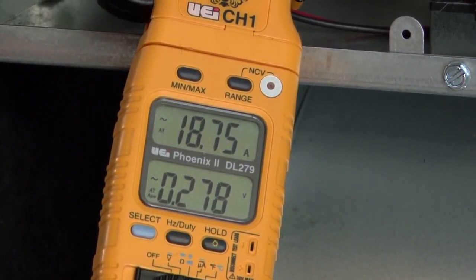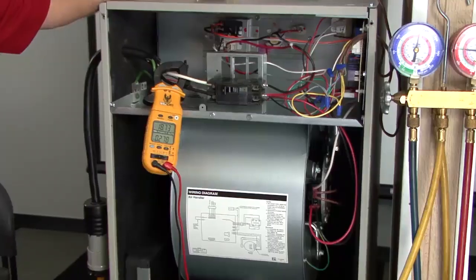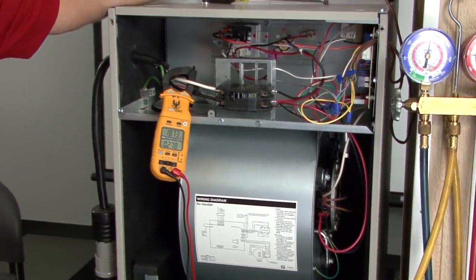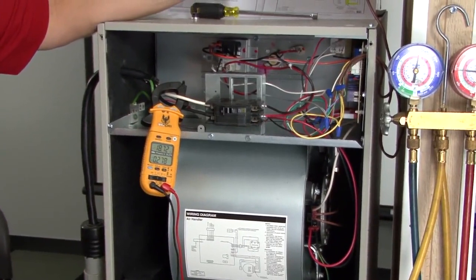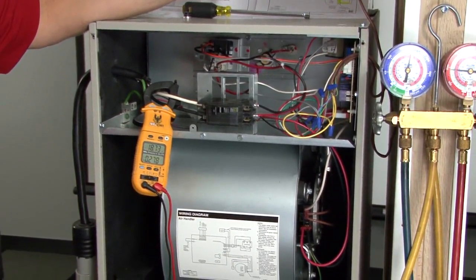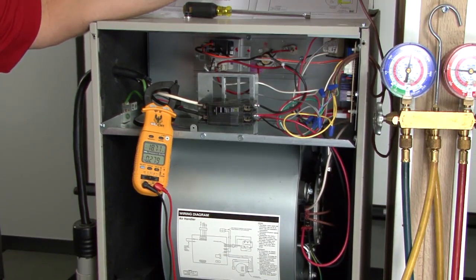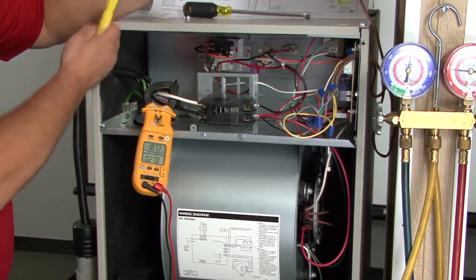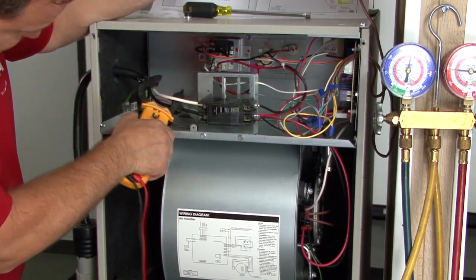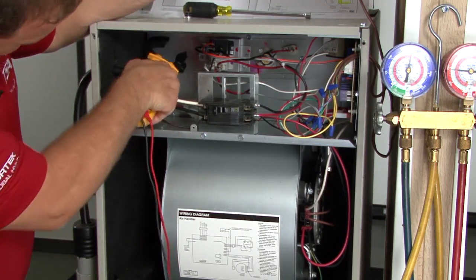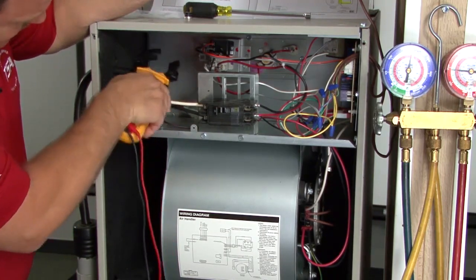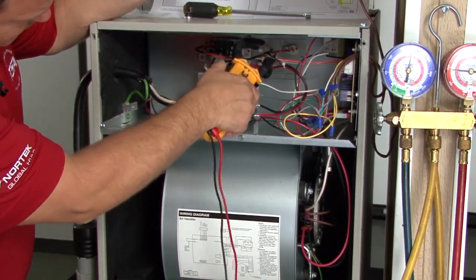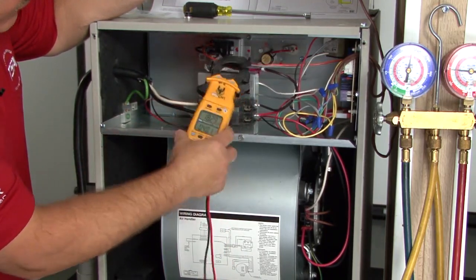This is 208 voltage supply coming into this building. But typically, residentially, you're going to have a 240 volt supply, and you're going to be close to 20 amps. So we can do it one of two ways. We can check the amp draw going into the entire heater kit, where this amp probe is showing right here. The other thing we can do is individually check the elements, especially if you have more than one element. So what you would do there is just find your wires. You can either go all the way up inside there and catch it right on the heater kit, or follow the power wire coming from the breaker to each bank of electric heat.